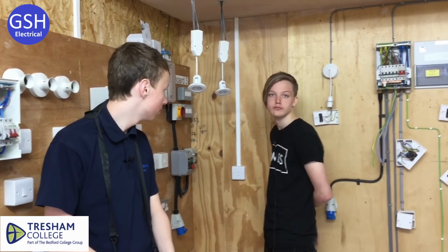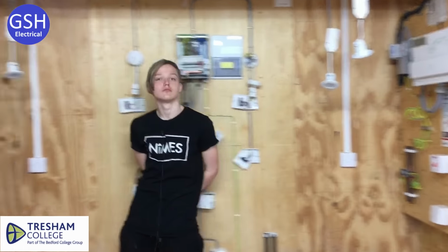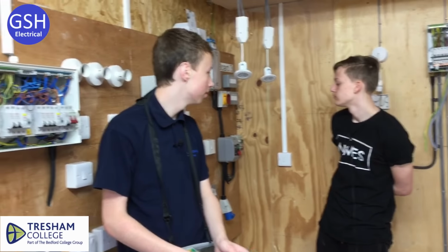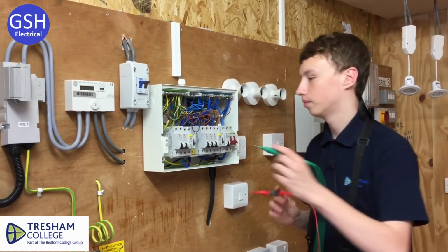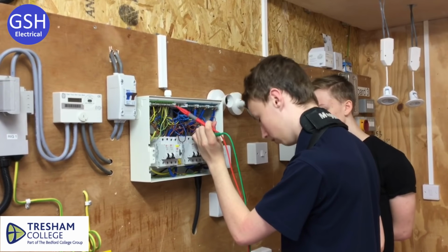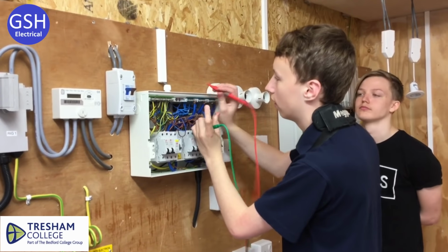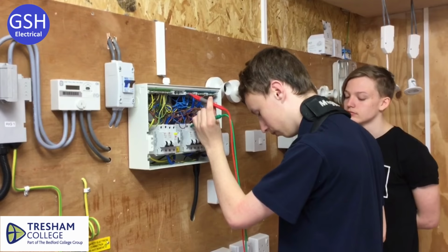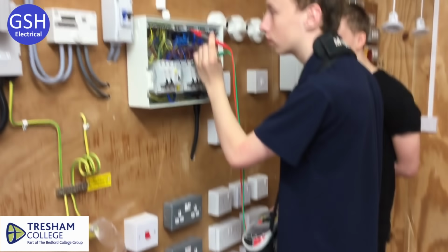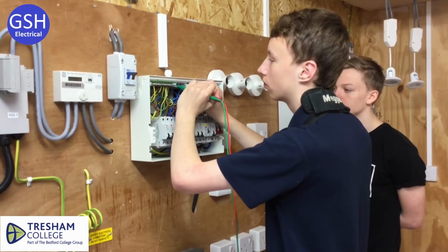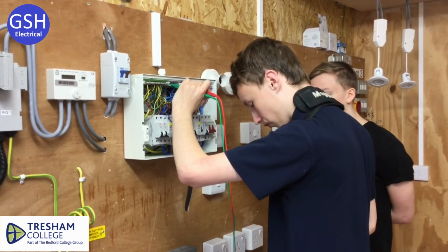However, with two-way switching, have we completed the insulation resistance test? No. So operate that one, and then you're going to do what? And the circuit now is back into which position? On. Harry's just operated both those switches. So now what is in circuit that wasn't last time? The other strapper. Let's do the test again for me then, please. 999. All of them 999. Good.